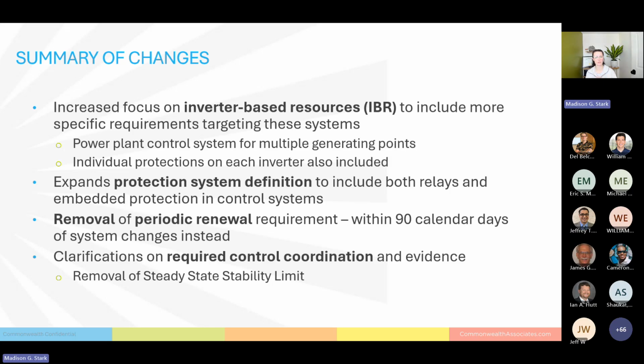It also clarifies some of the points about what the required control coordination involves and what evidence there is. So in this specific example, they're removing the steady state stability limit portion. Why that matters is they got a lot of feedback from generator operators that this steady state stability limit you were calculating was kind of a manually calculated thing. The steady state stability limit is very dependent on what the grid is doing as far as frequency and voltage, compared to what the generator is doing. So because of the grid itself and the voltage controls outside of the generator, calculating this steady state stability limit to put on a single graph for coordination isn't really helpful or accurate in determining coordination. It's something that changes, has flux in it, and varies.